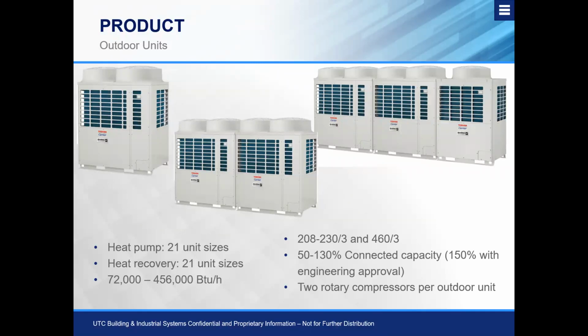So with the heat pump and the heat recovery models, we have 21 different unit sizes and configurations that we can work with depending on what kind of unit is needed for that job. They range from 72,000 all the way up to 456,000 BTUs. What configuration we use, as you can see above, depends on whether we have a single or triple configuration. These are available for 208/230 3-phase and 460 volt 3-phase applications. And we have a 50% to 130% connected capacity limitation on there, and you can get up to 150% with carrier factory engineering improvement.